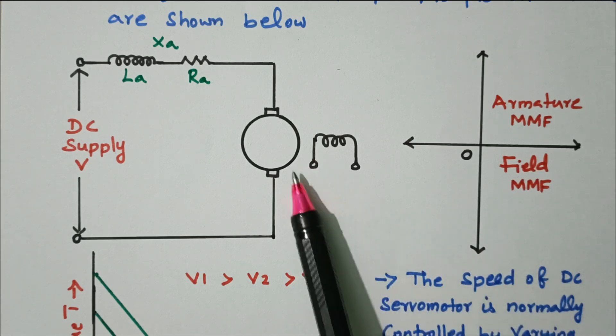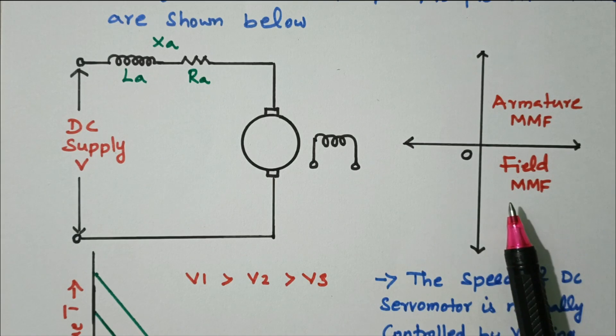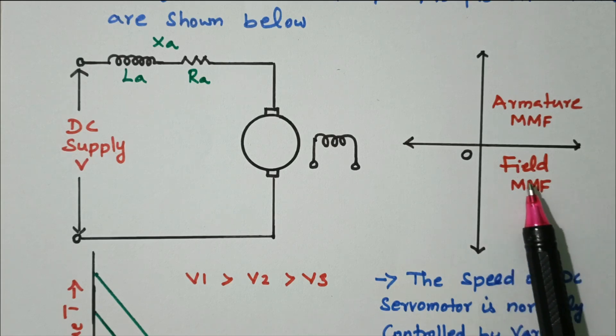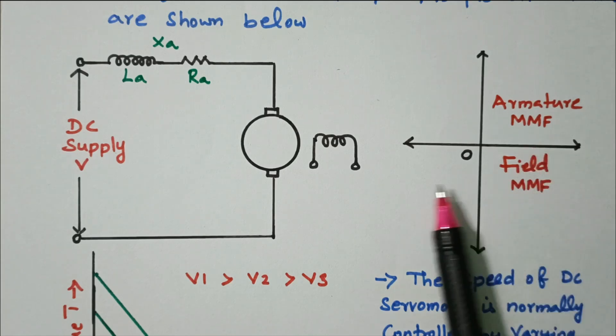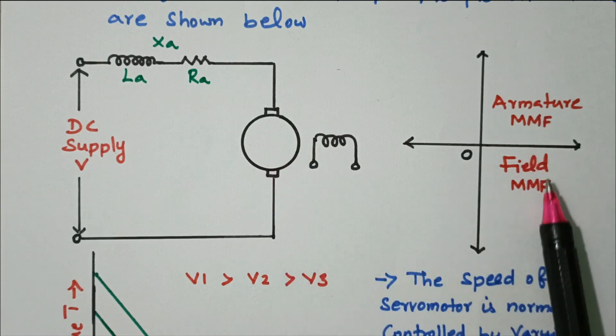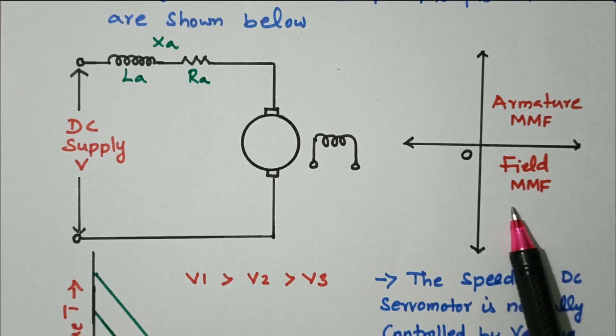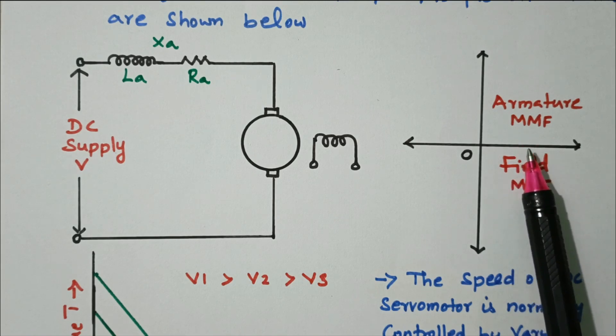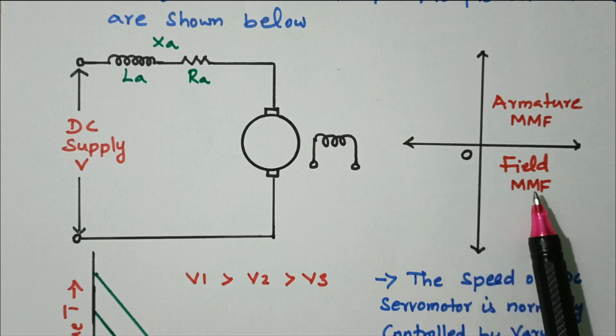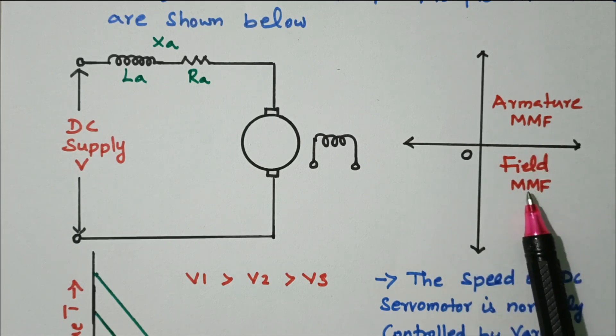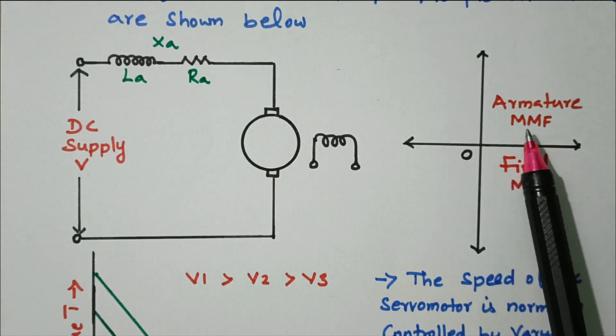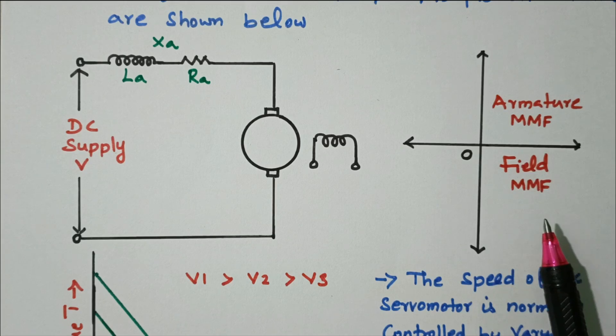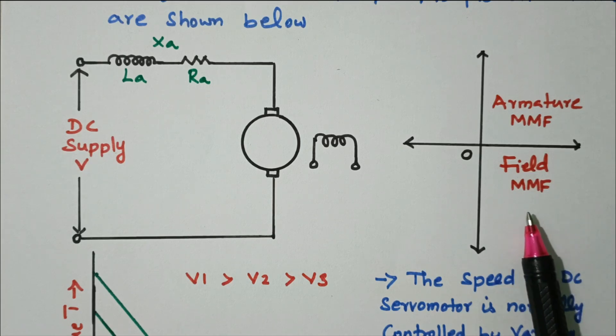This is not a continuously rotating machine — it is a position control motor. Wherever needed, it will rotate either in the forward or reverse direction to reach the required position. Any small change in armature MMF will be reflected in the speed of the motor. Because both MMFs are in quadrature, any small variation will be reflected in the position of the motor, which is why it is used for position control.